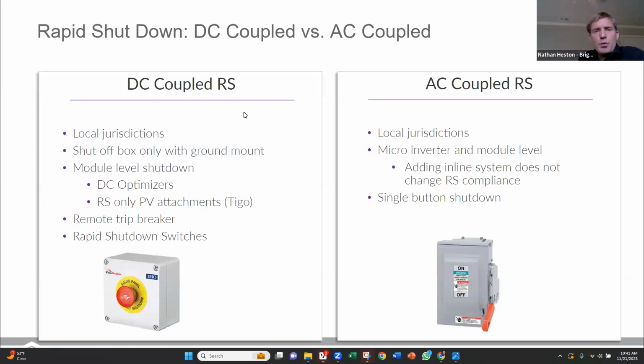If you have rooftop solar, it's important that you be able to shut off the solar array on the roof. Imagine there's a fire in the house and there's sunlight out there, and those panels, you've got a couple of wires hanging down through the roof, melted off vinyl that's covering them. Essentially, you have exposed wires that could injure firefighters. And so to be able to shut systems off at the module level, we need what are called rapid shutdown devices.